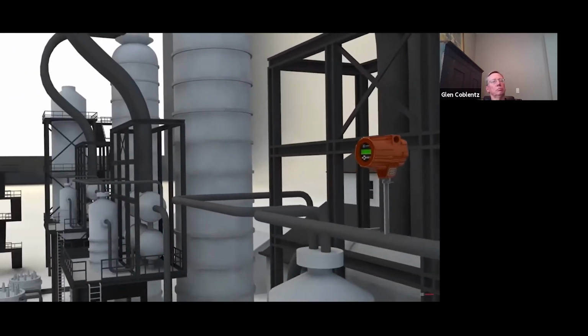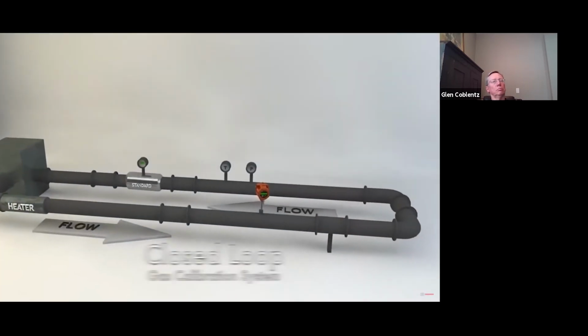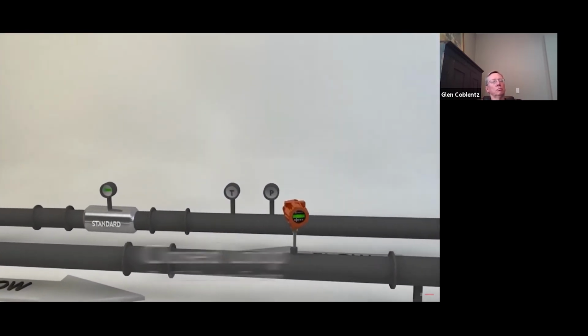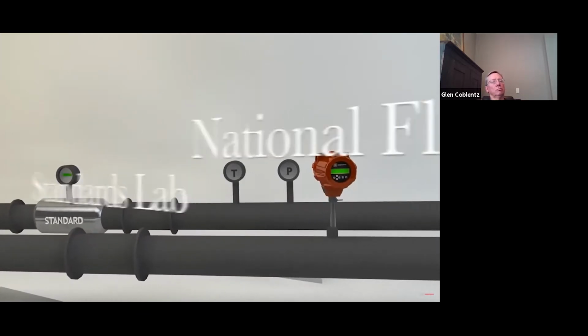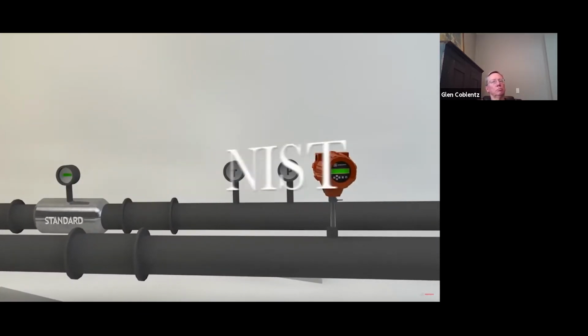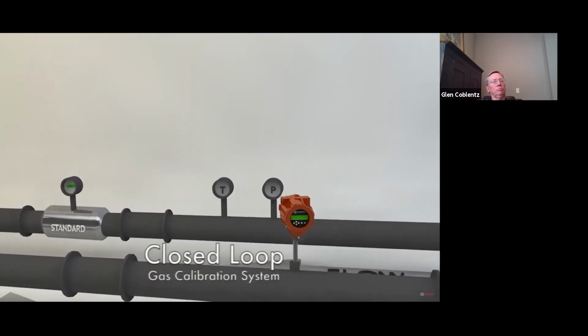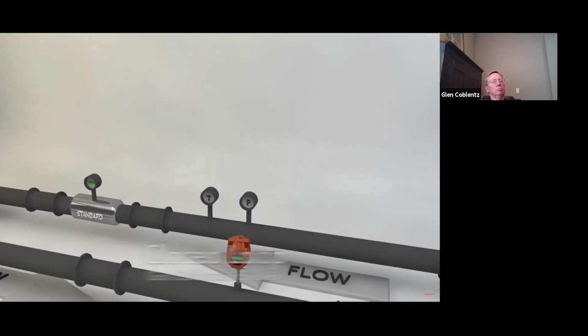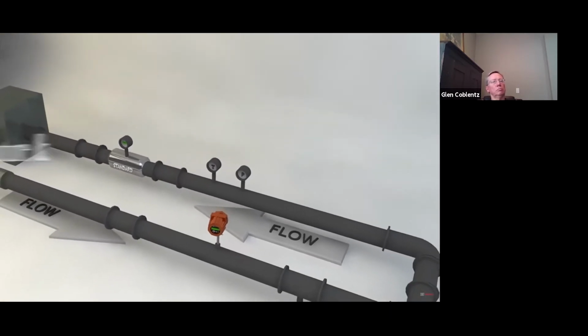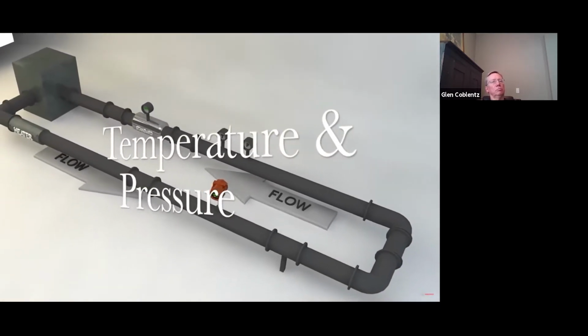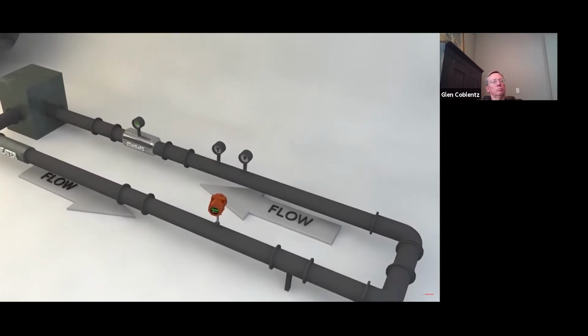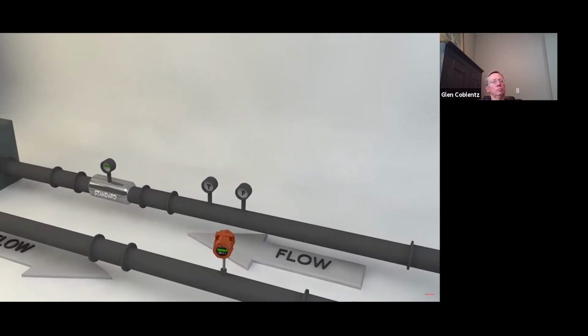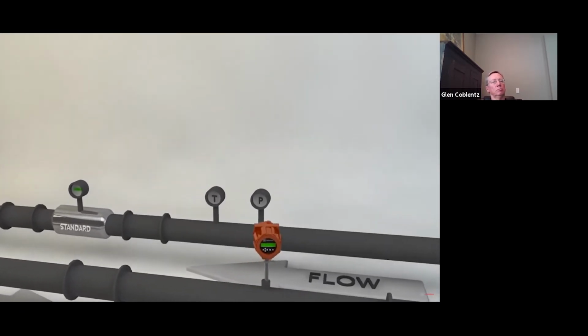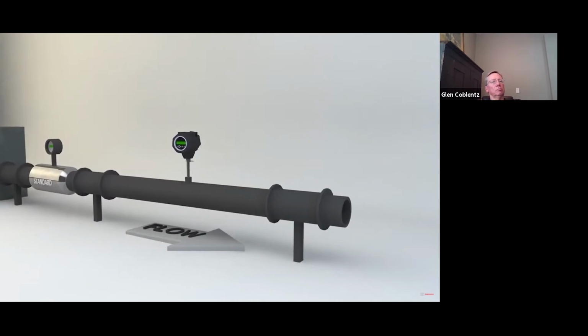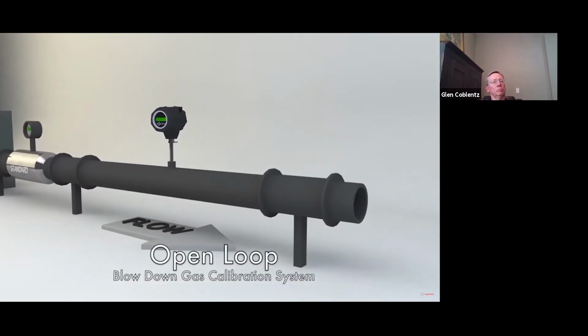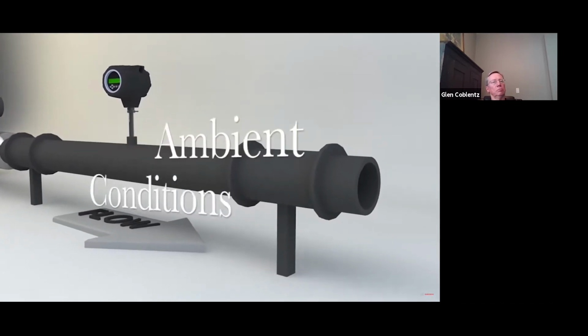Thermal mass flow meter manufacturers must assure that the instrument is calibrated on a closed-loop gas calibration system that is traceable to a national standards laboratory, such as NIST for the United States. Sierra Instruments uses a state-of-the-art NIST traceable closed-loop gas calibration system that is charged with the actual gas to be measured and set to the actual temperature and pressure of the end-user application. This perfectly simulates the customer application environment for a quality calibration, assuring the highest possible performance in the field. Be careful of blow-down or open-loop calibrations, as they operate at ambient conditions and are only done on air.